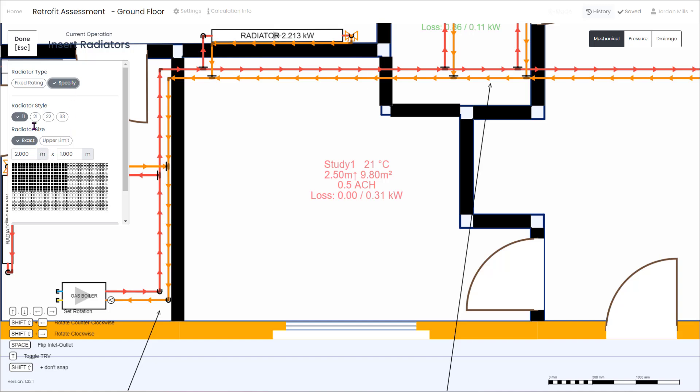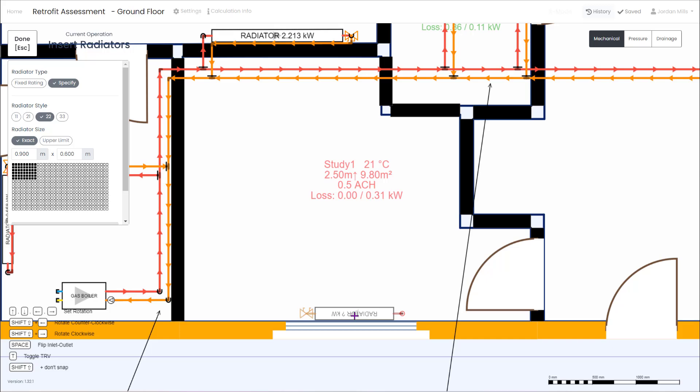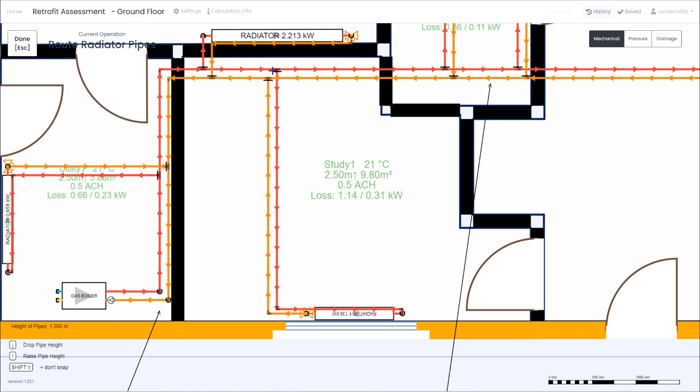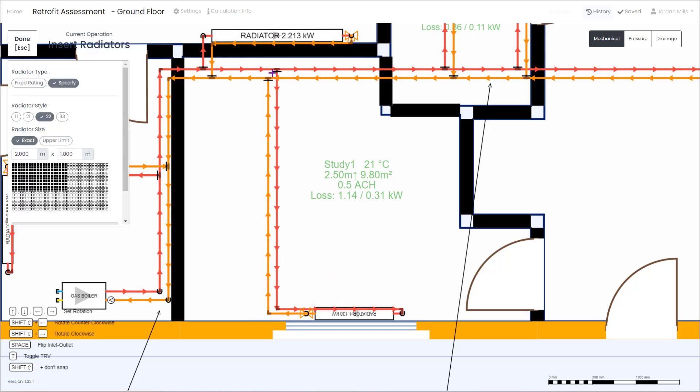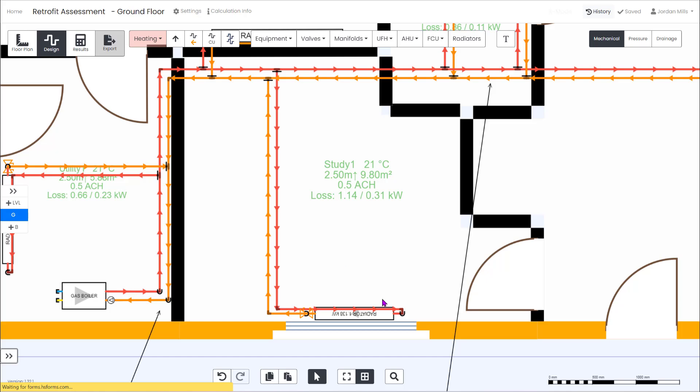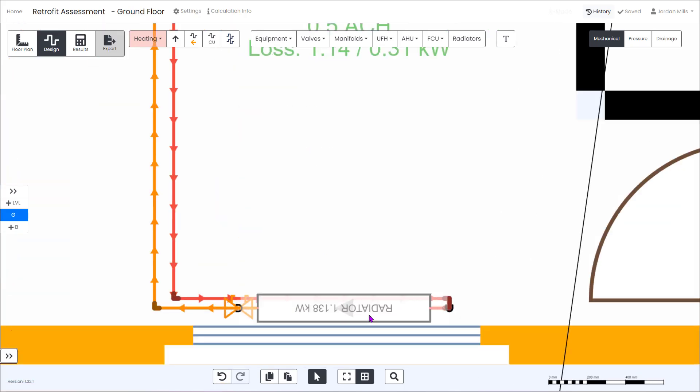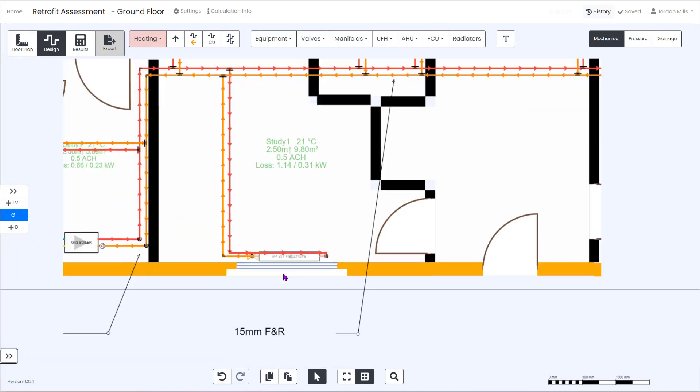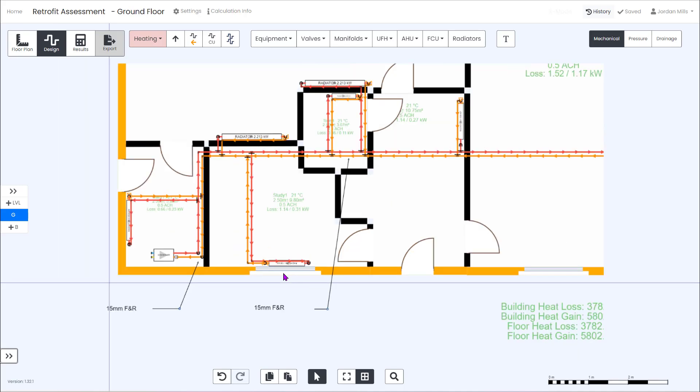For the study it's a pretty small room with a heat loss of 0.31 kilowatts. H2X gives you the ability to specify the existing radiator type and size. For this room it's an 800 by 600 type 22. We can see that based on a DT50 this gives us a 1 kilowatt output which is more than adequate for the current room.